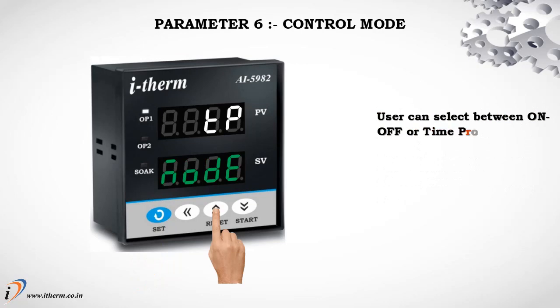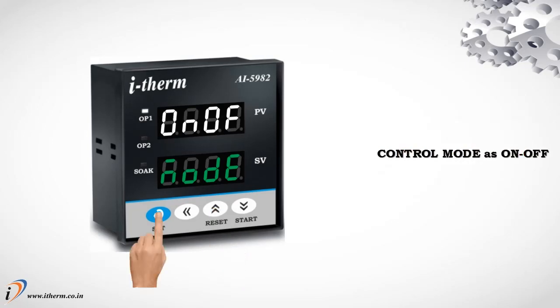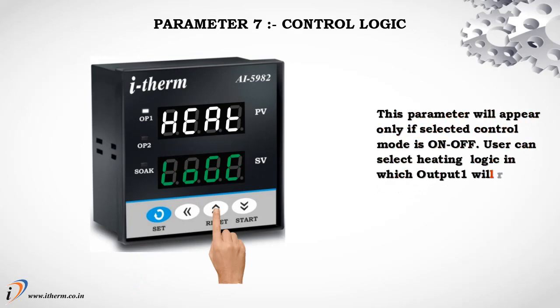Parameter 6: Control Mode. The user can select between on/off or time proportional action algorithm to be adopted for output. Parameter 7: Control Logic. This parameter will appear only if the selected control mode is on/off. The user can select heating logic, in which output 1 will remain on till the process value is less than the set point.